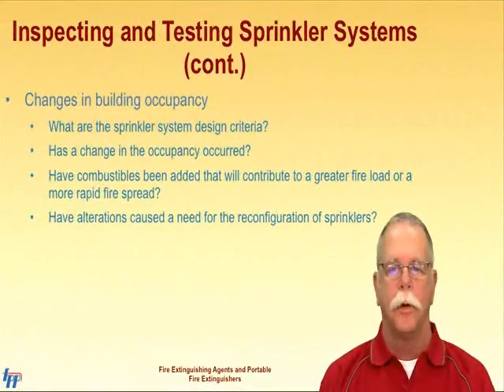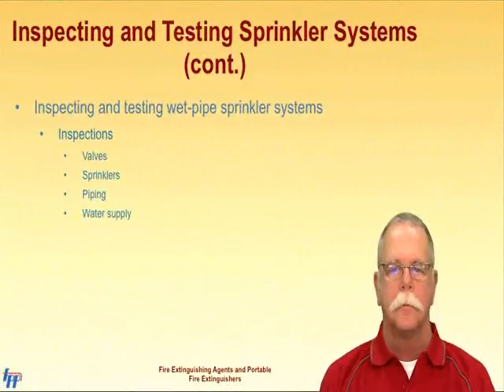Every time you enter a sprinkler-protected occupancy that has changed business, the first thing you should wonder is, did they update and upgrade the sprinkler system? This is a leading cause of sprinkler system ineffectiveness, and it is completely preventable. When inspecting wet systems, or any time you look at a sprinkler system, you should make sure the control valves are open, and if they are not open, report it immediately.